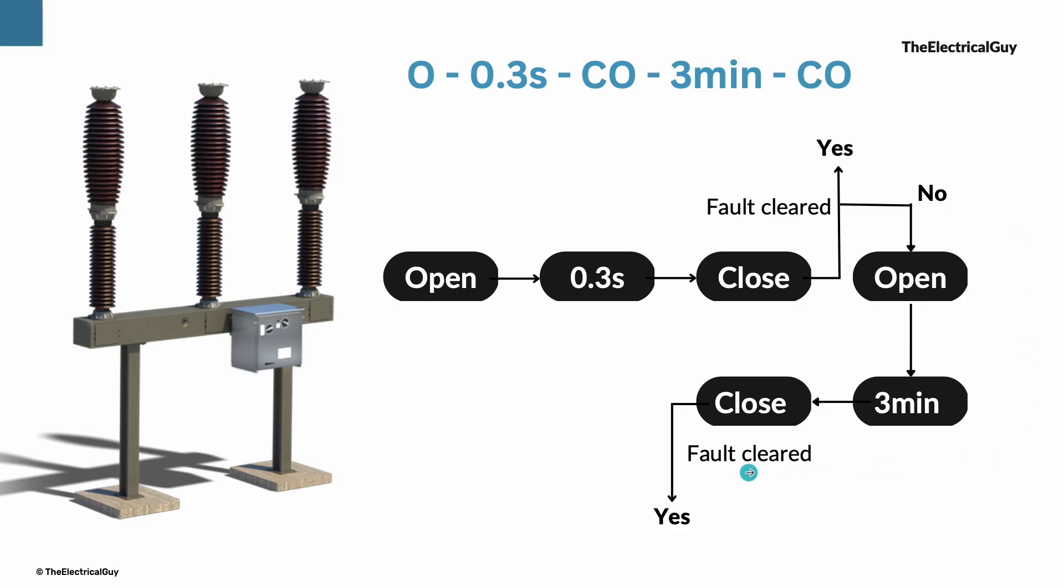Again if the fault is cleared, then the breaker will remain closed. If the fault is still not clear, then again breaker will get an opening command and now it will remain open unless closed manually.